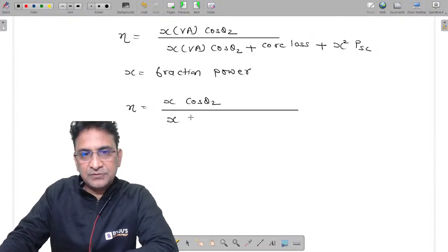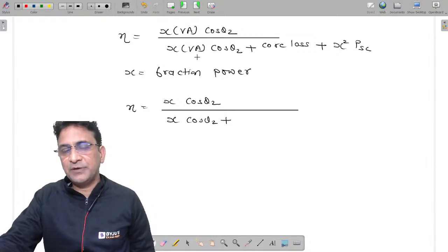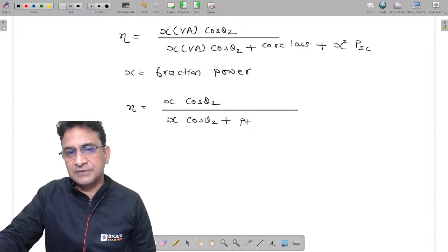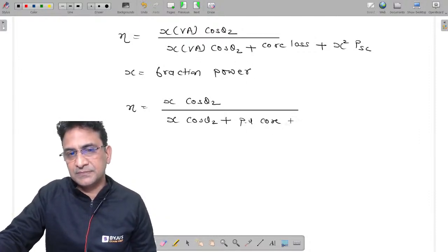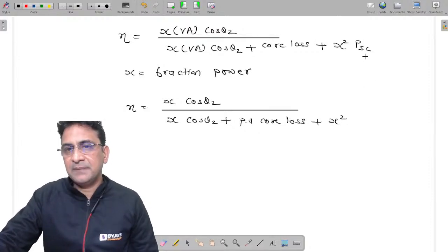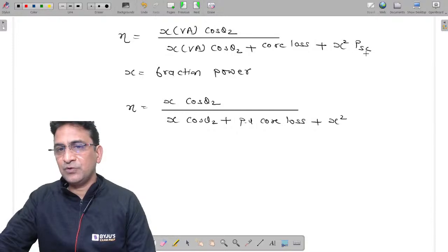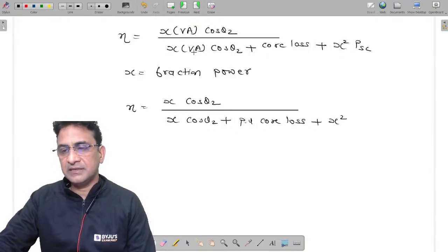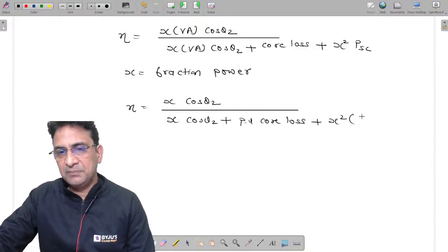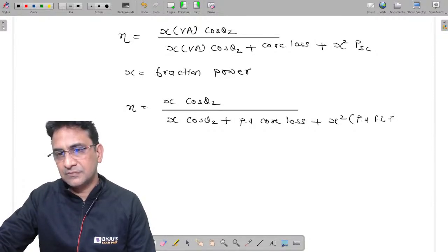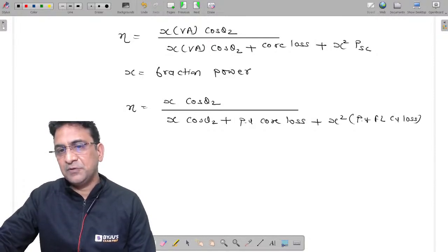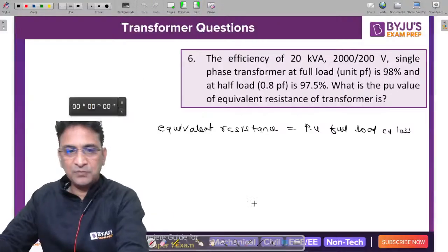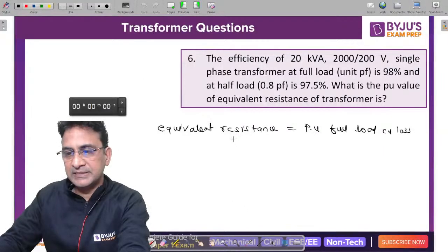X into cos theta 2. If core loss is divided by the rated volt ampere, it becomes the per unit core loss, plus X square times PSC, that is the full load copper loss, divided by the rated volt ampere. It becomes the per unit full load copper loss. And we have to find the per unit full load copper loss because it is the same as the equivalent resistance.